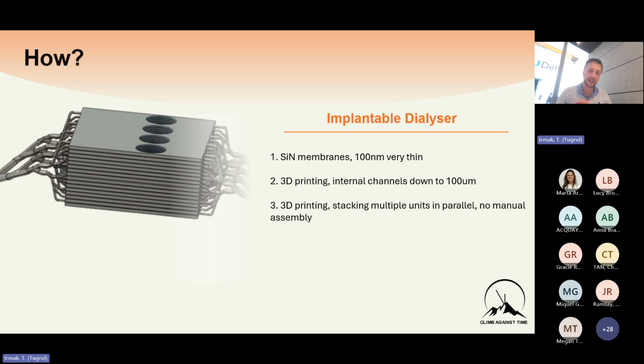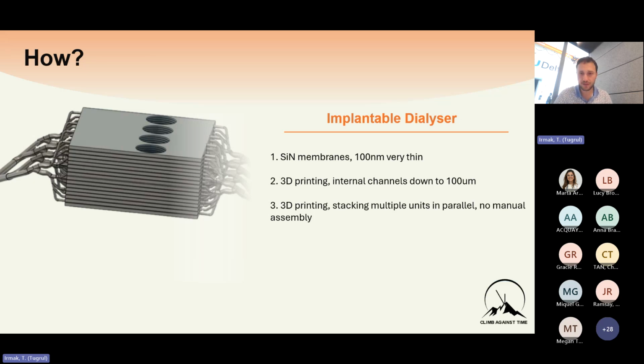The reason why current dialyzers are made as they are with the hollow fiber bundles is because you can get a bundle of fibers and you can pot them in polyurethane and that's it. And then you cap it, you have basically leak-free. There's no possibility of leakage. But if you want to have individual flow distribution into such fibers, that's difficult with conventional manufacturing. And that's exactly what you need to limit this turbulence in such a device, which you would need for an implantable.